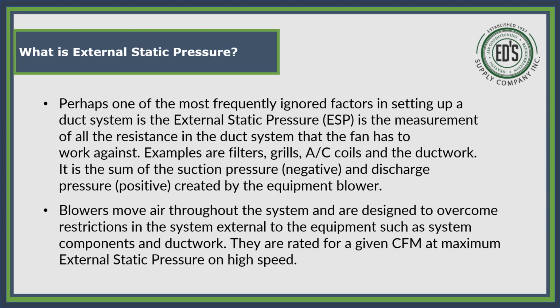Perhaps one of the most frequently ignored factors in setting up the duct system is the external static pressure, or what we're going to call for short ESP. It is the measurement of all the resistance in the duct system that the fan has to work against. Examples are filters, grills, AC coils, and the ductwork. It is the sum of the suction pressure, which is negative, and discharge pressure, which is positive, created by the equipment blower, which is your blower motor.